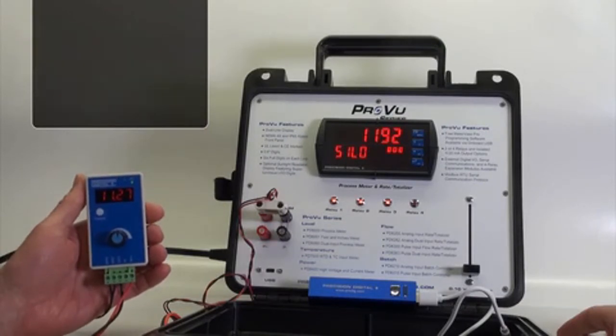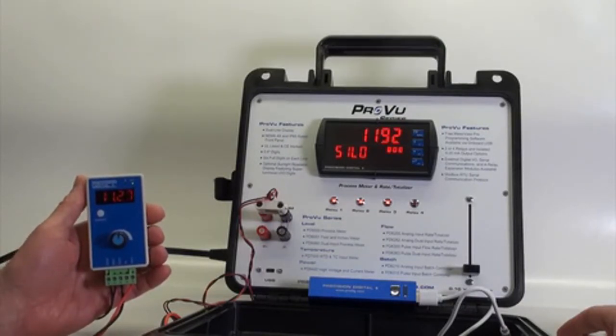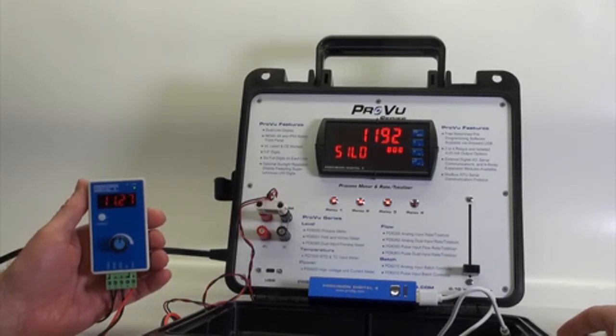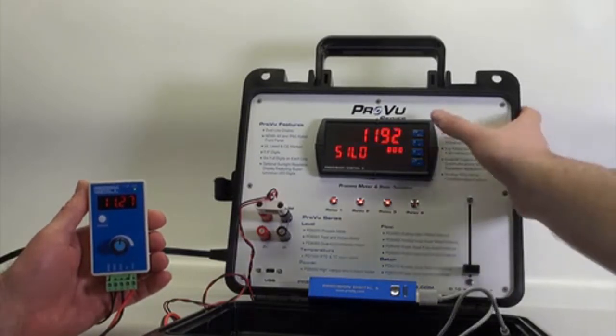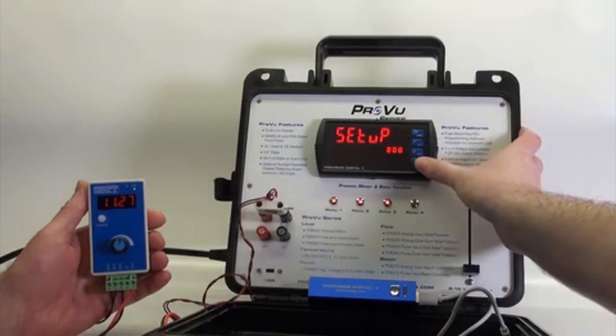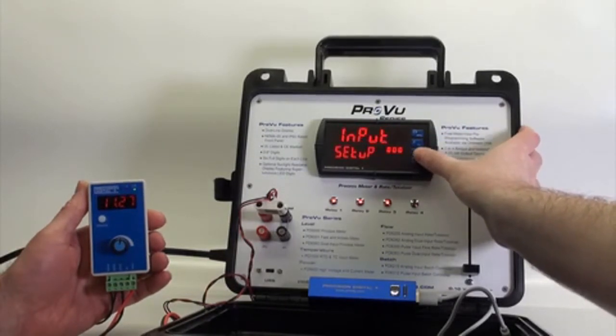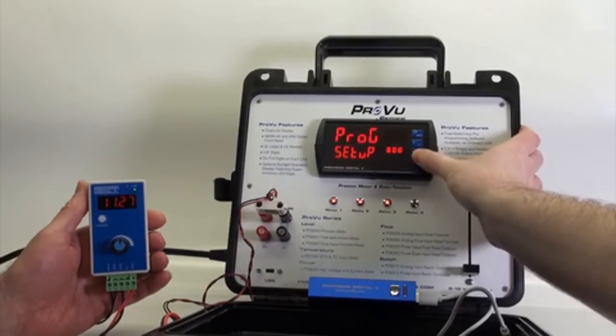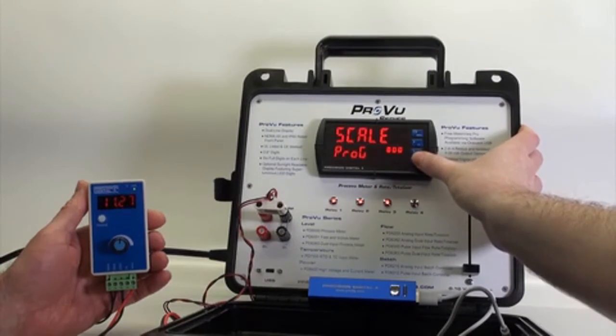So what we have here is the PD9502 connected to a PDD 6000 demo, and we're going to demonstrate how you can quickly calibrate a device using the PD9502. We're going to program the meter to take in a 4 to 20 milliamp signal, then go to the internal calibration feature.